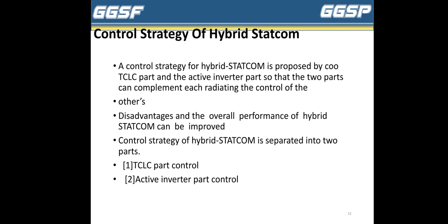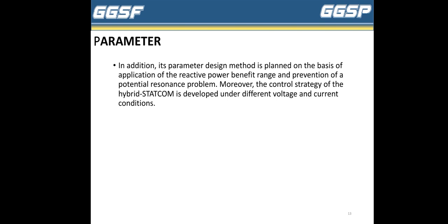The control strategy of the hybrid STATCOM is separated into two parts. The first one is the TCLC part control and the second one is the active inverter part control. Next is the parameter design. In addition, the parameter design method is planned on the basis of the application of the reactive power compensation range and the prevention of the potential resonance problem. Overall, the control strategy of the hybrid STATCOM is developed under different voltage and current conditions.